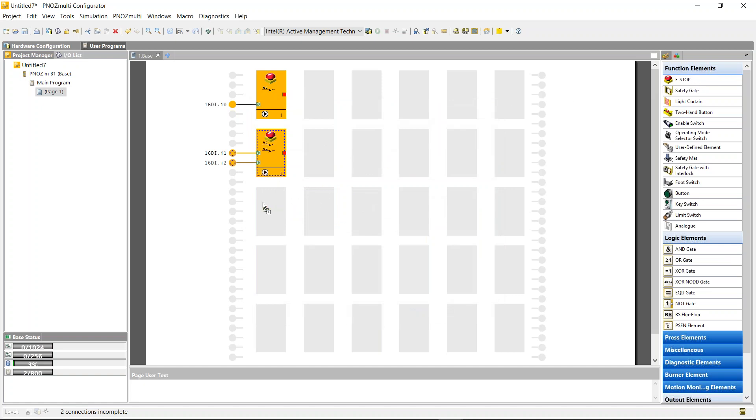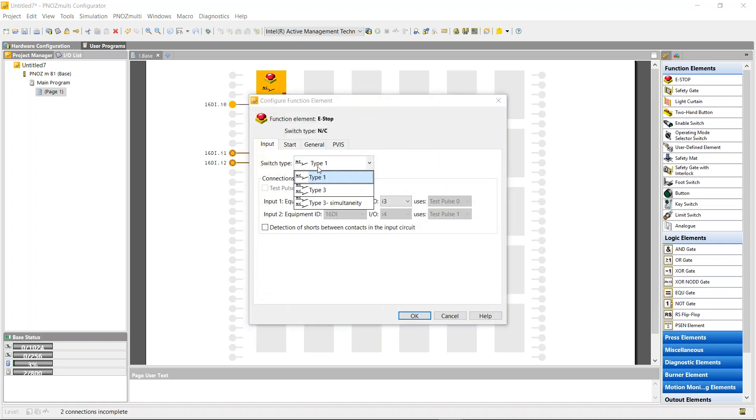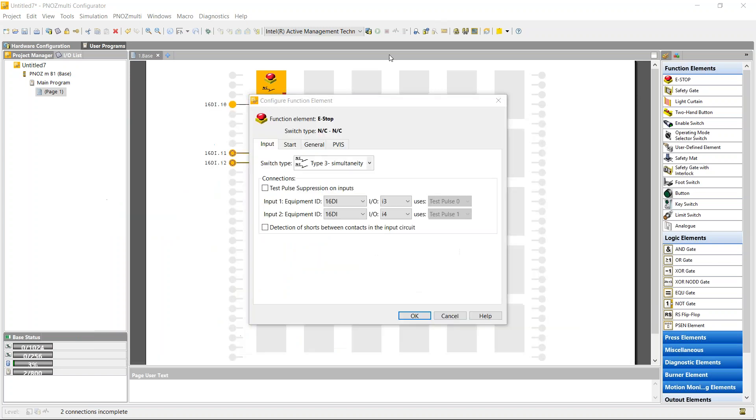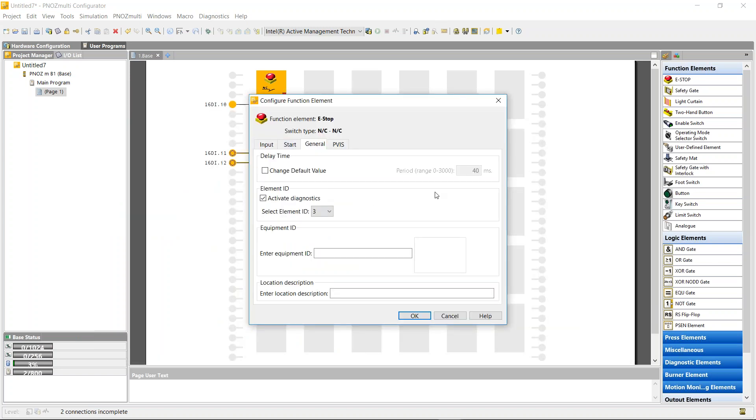The third one I'm going to use is type 3 simultaneity. Simultaneity is monitoring the channels and the time between each channel turning on. It gives you a max of 3 seconds from channel 1 on the e-stop to channel 2 turning on. If the time is quite large, it detects it as a fault inside the logic. I can adjust the simultaneity default value from 40 milliseconds all the way up to 3000, but I'm just going to leave it at the default for now.